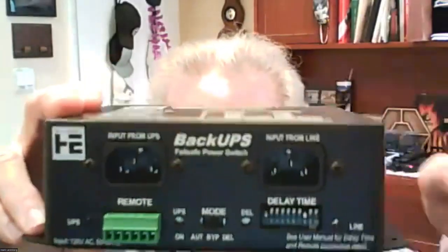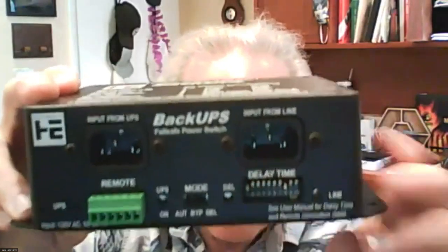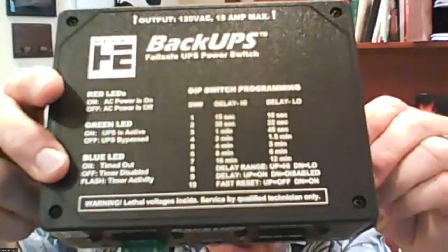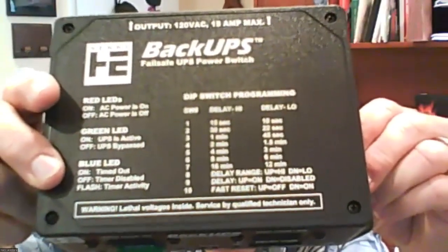We have a dip switch on the front here. By setting those dip switches, you can program a restart delay time period so that when the UPS comes back on, it waits and monitors the UPS output to be sure it's stable before putting the UPS back online. That prevents it from going back online if the output becomes unstable.